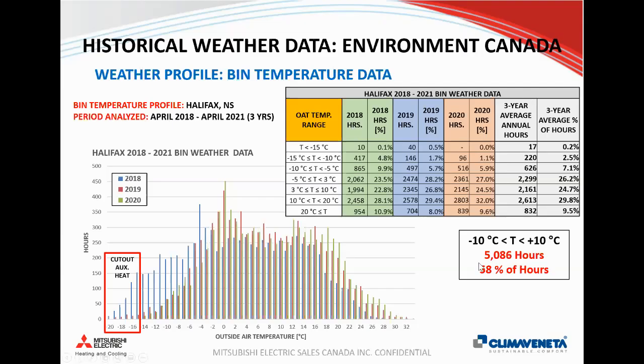So just showing here for Halifax, between -10 and +10 degrees Celsius outside air temperature, there's 5,000 hours on average that Halifax sees at that temperature. That's 58% of the total number of hours in the winter that they're spending between -10 and +10. So if you forget about the need to run an auxiliary boiler below -10, you can still cover off a significant portion of the heating hours with an air-to-water heat pump and eliminate the natural gas that you're going to use in a boiler.